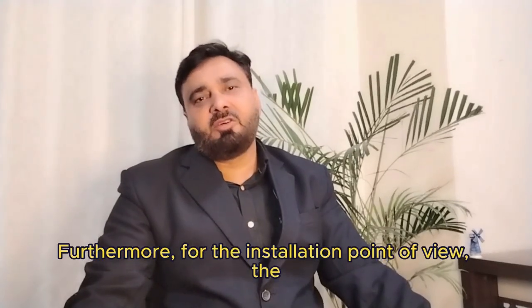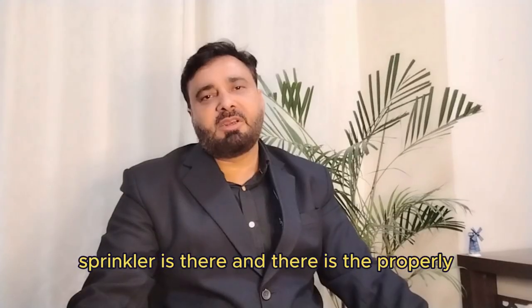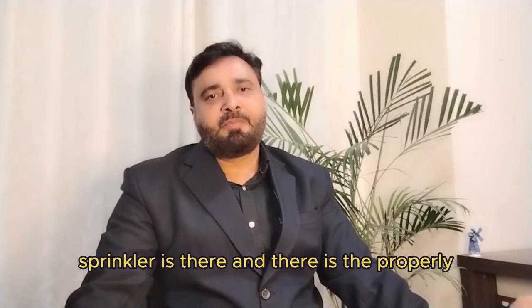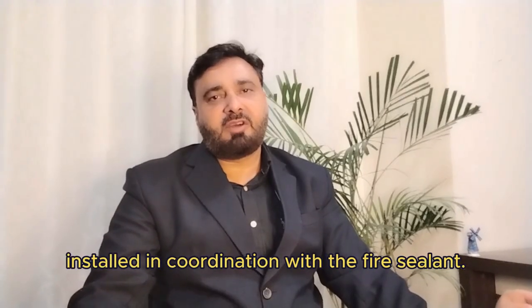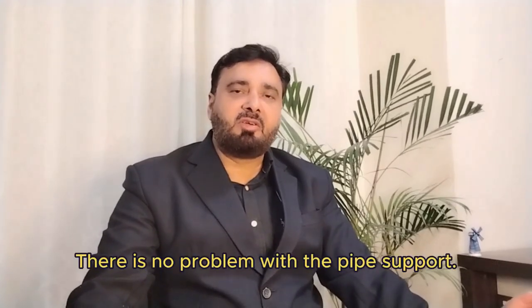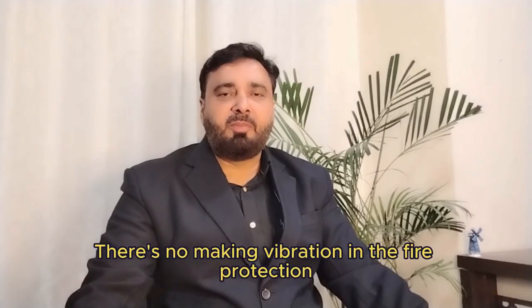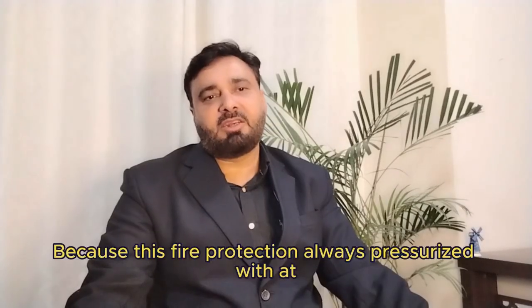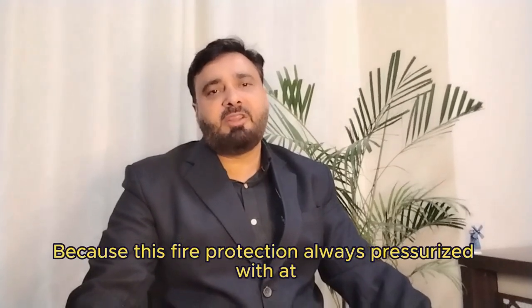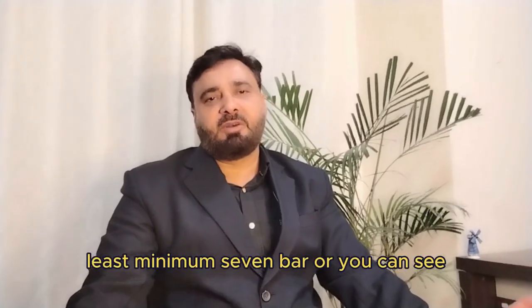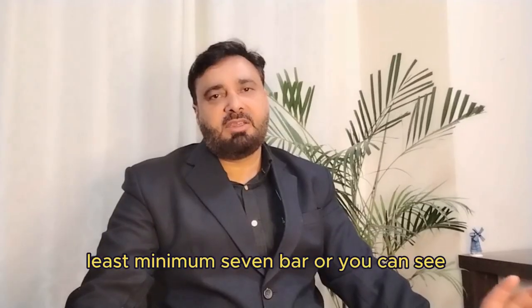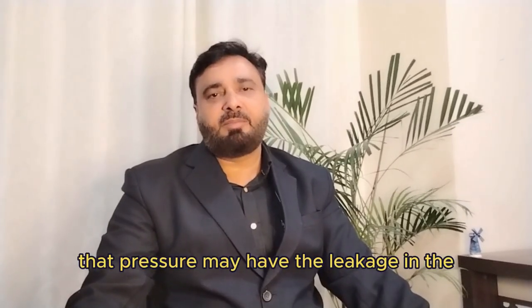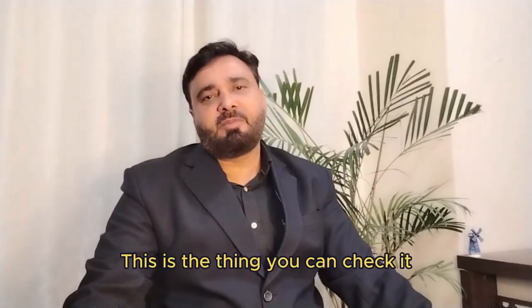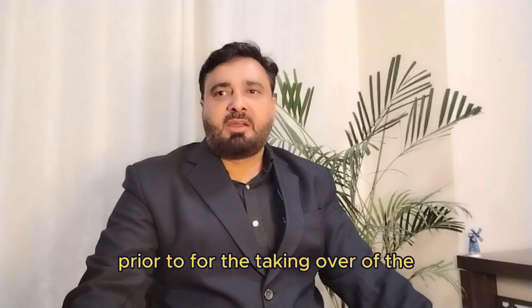Furthermore, from the installation point of view, the sprinkler installation must be verified, that all sprinklers are there and properly installed in coordination with the fire sealant. There is no water leakage from there. All pipes are individually supported. There is no problem with the pipe support. There is no vibration in the fire protection pipe, because this fire protection is always pressurized with at least a minimum of 7 bar, and that pressure may cause leakage in the pipe if it is not properly sealed and installed. This is the thing you can check prior to taking over the villa.